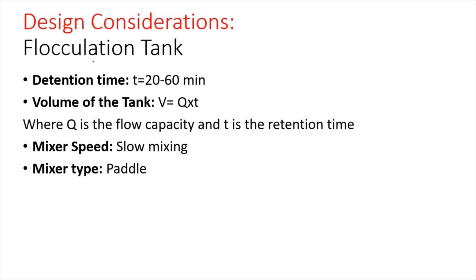Now for the flocculation tank, the detention time is much higher. It's between 20 to 60 minutes. The volume of the tank is also V equals Q times t. And here we are using a slow mixing, and the mixer type must be a paddle mixer.